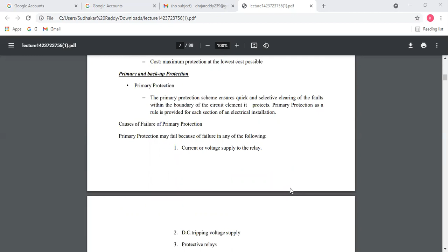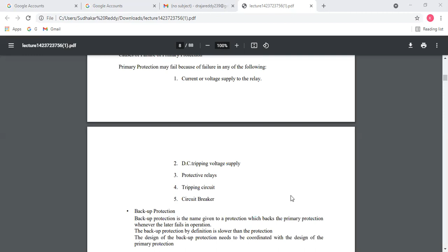Next one, backup protection. Backup protection is the name given to the protection which backs up the primary protection whenever the primary protection fails in operation. The backup protection by definition is slower than the primary protection. The design of the backup protection needs to be coordinated with the design of the primary protection.